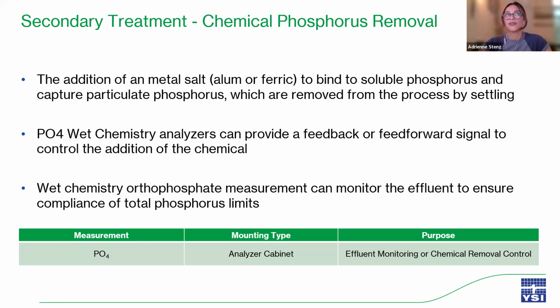A feedback or feed-forward control system using an orthophosphate analyzer is often used to control chemical dosing for phosphorus removal, reducing excess chemical use and saving money for a facility. So many facilities see an ROI of 1 to 2 years when adding an orthophosphate analyzer to automate this chemical removal process.